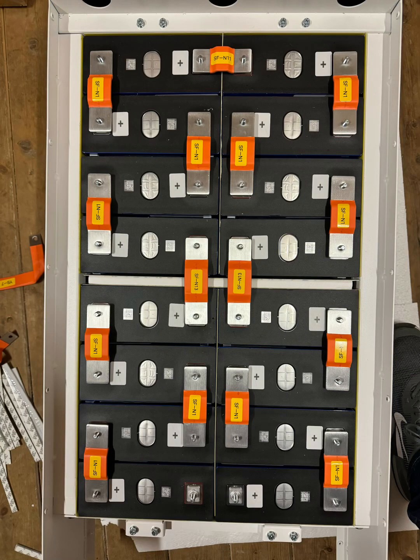Now for some reason I didn't take a picture of the bus bar layout, but here's one from the seplos unit which is identical. You can see bottom left is the first bus bar, working up from each positive all the way around to cell 16. Once the bus bars have been laid, you can then relay the terminals on top of this and tighten the nut that goes with these bus bars to 5 Newton meters on each one.